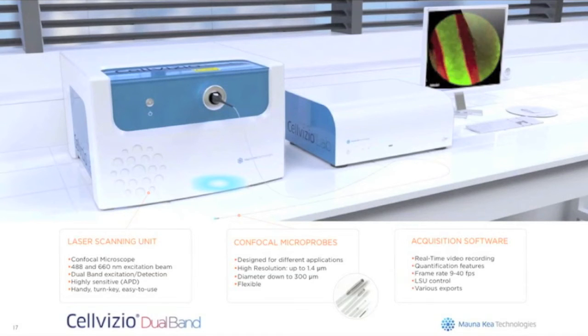On the left you have the laser scanning unit, so this is where you have all the optical setup. Then we have the computer with the control software that allows you to control the laser scanning unit and to perform the real-time video recording of the fluorescence of your sample. And a key element of the instrument is of course the confocal microprobe that is attached to the laser scanning unit. We have different confocal microprobes of different diameters and different technical specifications. The smallest microprobe diameter is 300 micron.